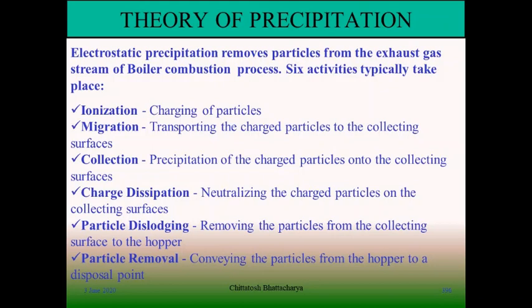ESP removes particles from the exhaust flue gas of boiler combustion products. There are six specific stages in the ESP for precipitation of dust particles: first, ionization — charging of particles; second, migration — transporting the charged particles to the collecting surfaces; third, collection — precipitation of charged particles onto the collecting plates; fourth, charge dissipation — neutralizing the charged particles on the collecting surfaces; fifth, particle dislodging — removing particles from the collecting surface to the hopper; sixth, particle removal — conveying the collected dust in the hopper to a disposal point.